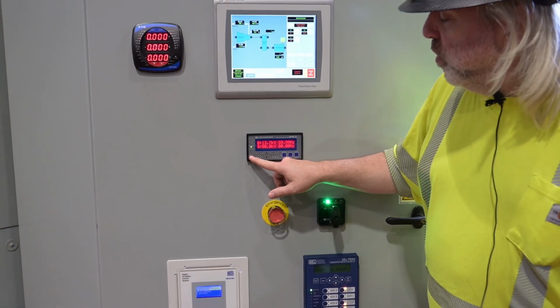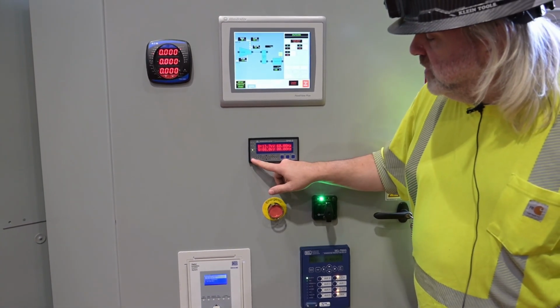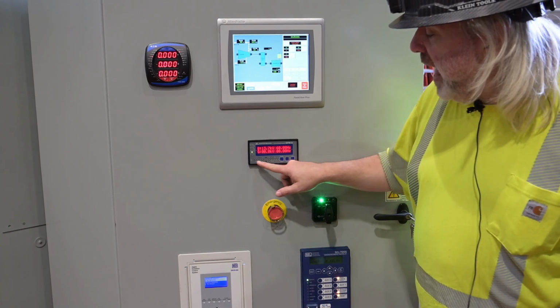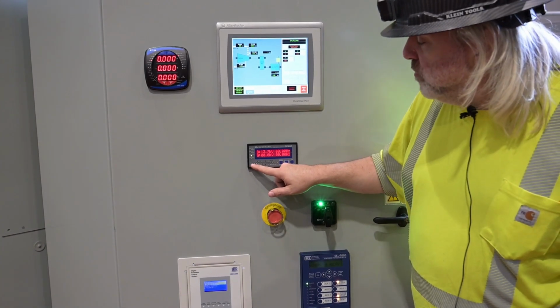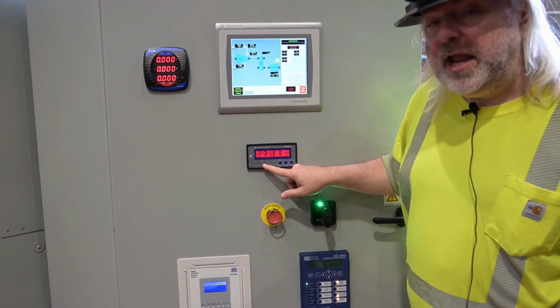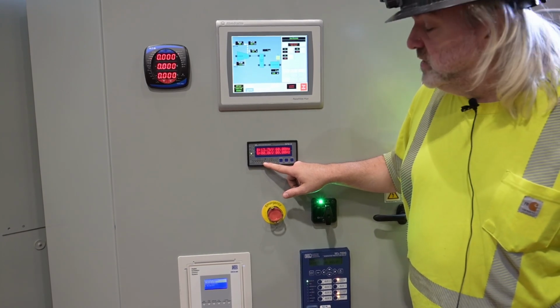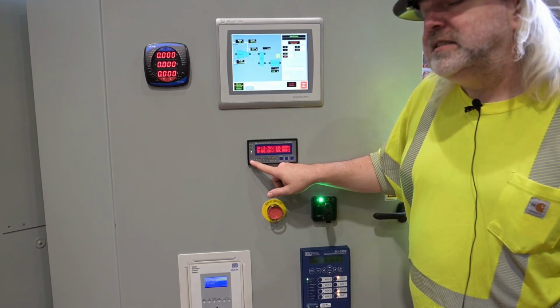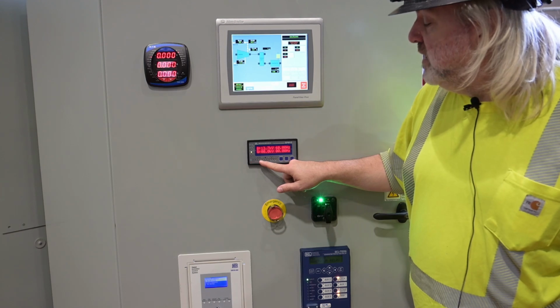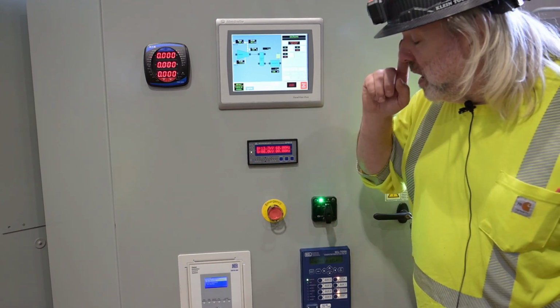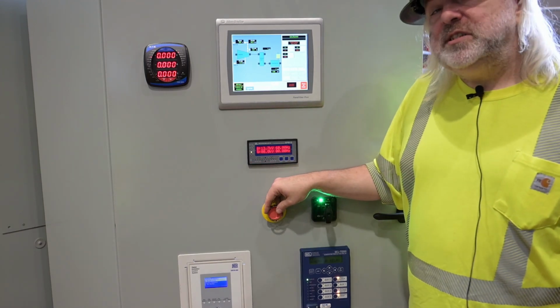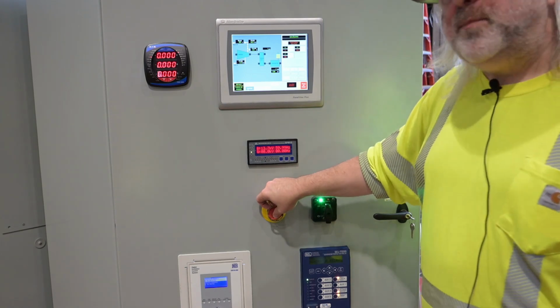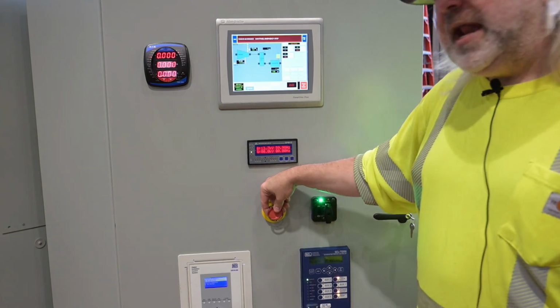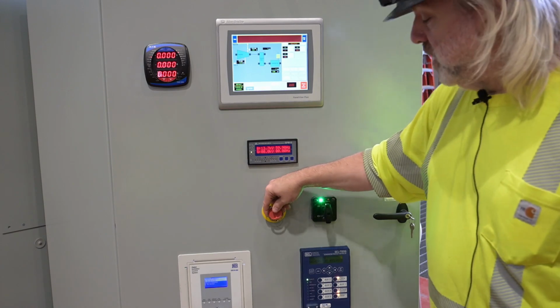Once we're there, we'll use this as a synchroscope. This line will light up red until it gets to the middle where it goes green. The middle means we're in phase. When we're synchronizing, we want to see this line going slowly in this direction. Underneath, we have an emergency stop button. Pushing the emergency stop in will trip the unit. Pulling it out will allow you to reset the unit.